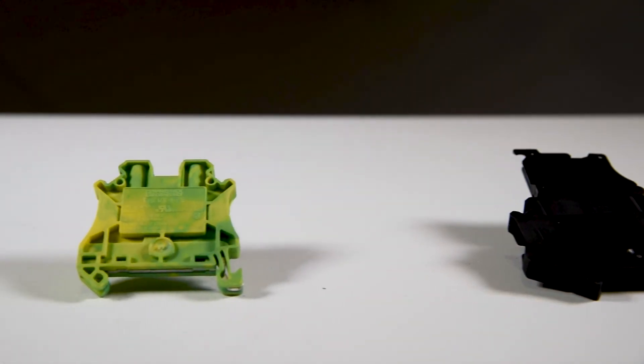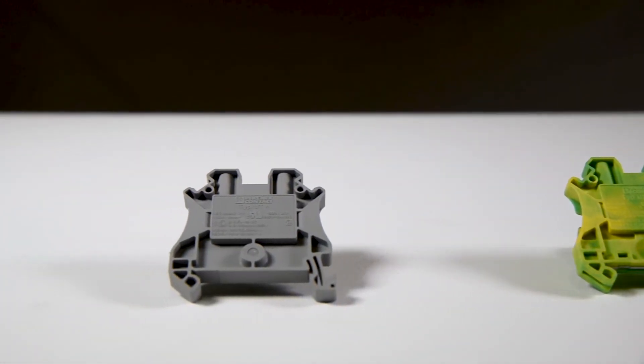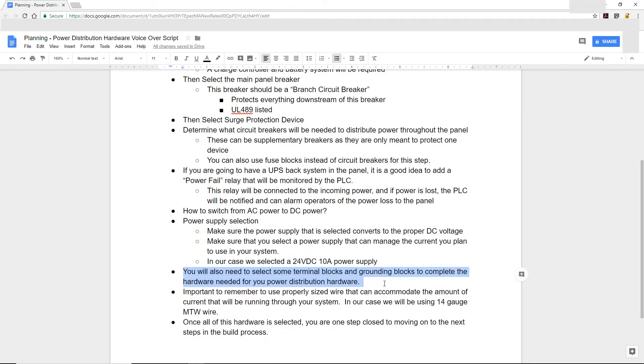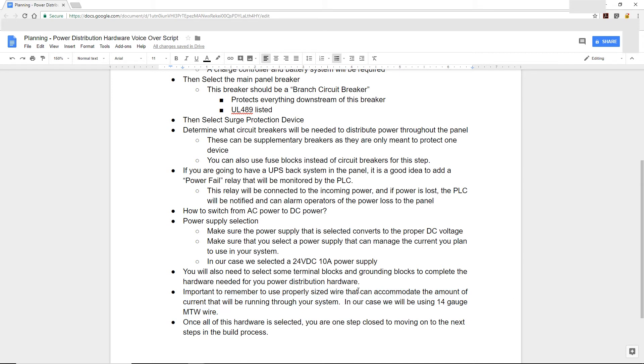We also need to select terminal blocks and grounding blocks to finish off our power distribution hardware selection. These are needed to run our neutrals and grounds through. We also want to make sure we're using the proper wire size in our power distribution to accommodate the current that's going to be running through our system. In our case, we typically use 14 gauge MTW wire, which is more than enough to accommodate the power we're putting through our panel. But you can increase to 12 or 10 gauge, or go down to 16 gauge, depending on your particular application.